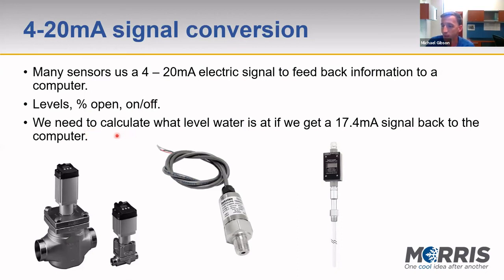So as an example, we were going to try to calculate the water level if we're getting a signal back to our machine that's 17.4 milliamps. But that doesn't mean anything to anybody by itself. Basically, the signal comes back as either 4, for an off or 0% result, or 20, for an on or 100% result. So I get a 17.4 and I don't really understand what that means. Is that good? It seems like it's mostly open, but I'm not sure.